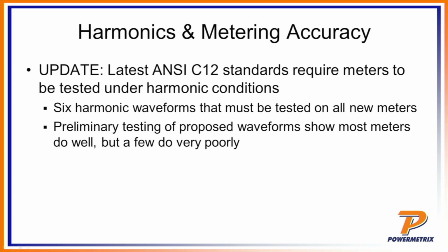Those 6 harmonic waveforms were made to represent 6 different harmonic loads seen out in the real world, which would be applied to each and every meter to guarantee consistent results. The reason that was a problem is that, historically, you could take 3 different VA hour meters, run them on the same load, and get 3 different answers, in some cases up to 50% different.